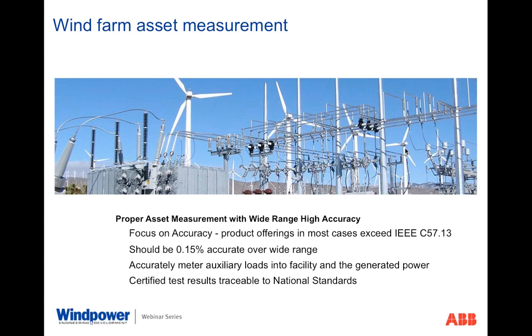So let's summarize what we've talked about here this afternoon and what's important. First of all, proper accuracy measurement is important. That's what you're creating this wind farm for, to get a return on investment. It's most important to do that as accurately as you can. So it should be recommended in the 0.15 accuracy class over a wide range. And remember, don't just specify 0.15s. Specify the range of currents you need to measure. And also remember that when you look at the auxiliary loads, factor in the facility needs as well as the losses in through the generator step-up transformer. And last but certainly not least, have certified test reports on hand traceable to standards.